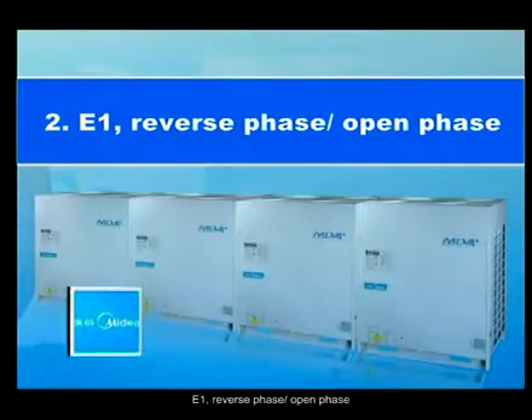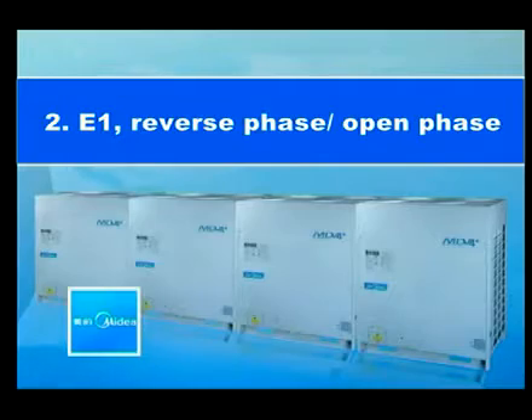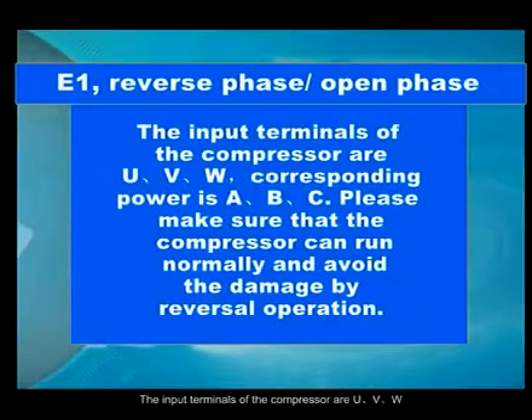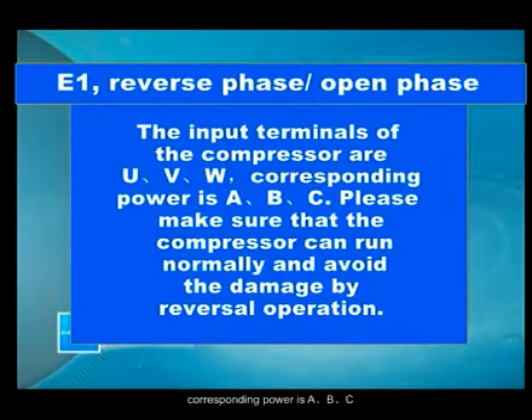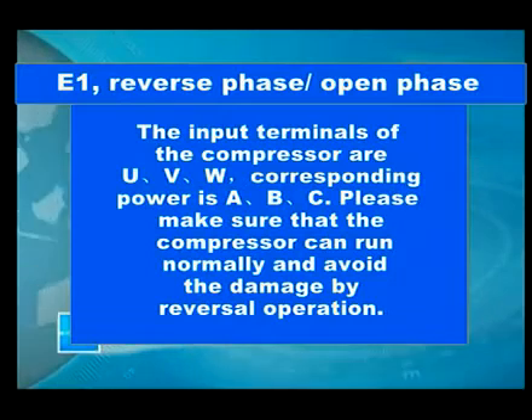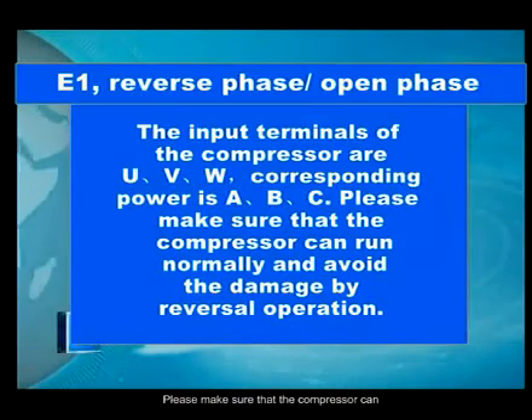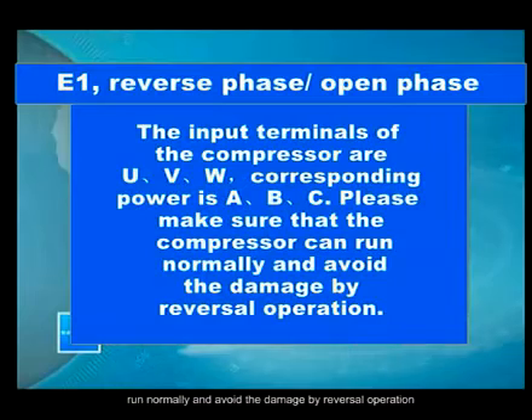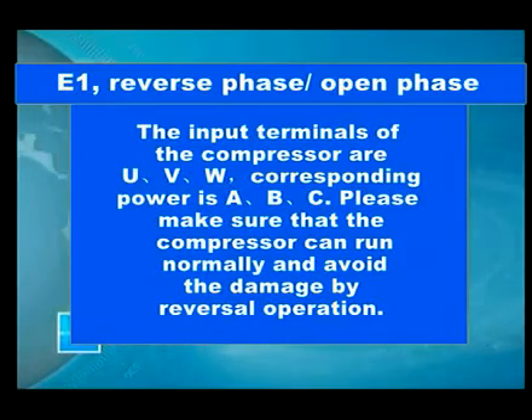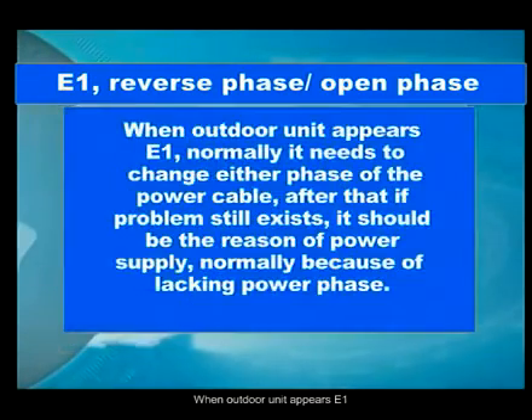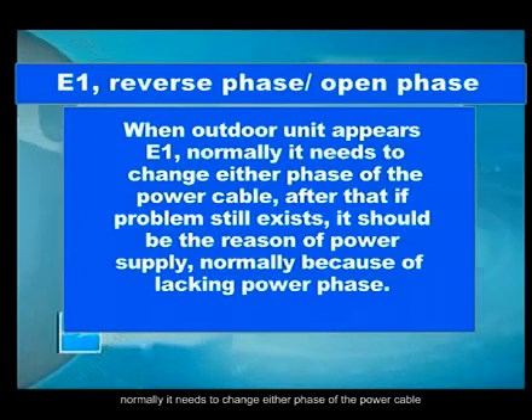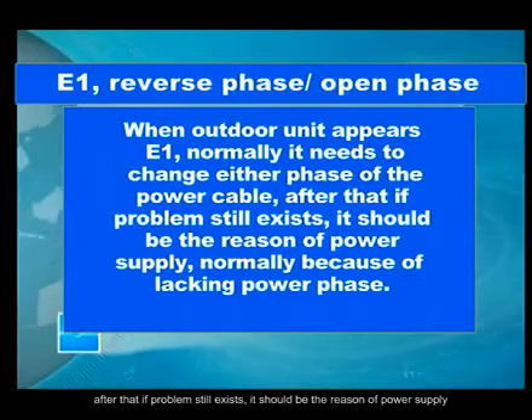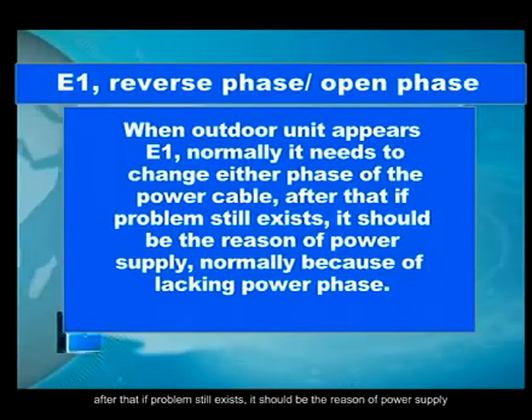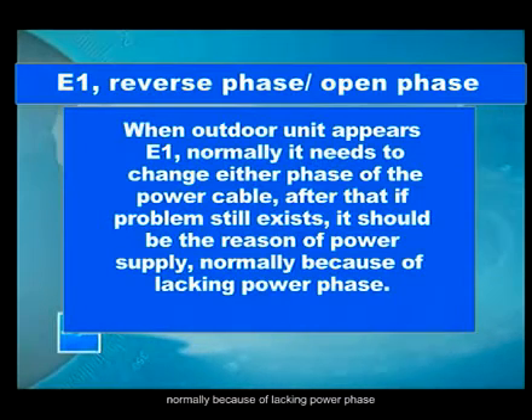E1. Reverse phase/open phase. Input terminals of the compressor are U, V, W. Corresponding power is A, B, C. Please make sure that the compressor can run normally and avoid the damage by reversal operation. When outdoor unit appears E1, normally it needs to change either phase of the power cable. After that, if problem still exists, it should be the reason of power supply, normally because of lacking power phase.